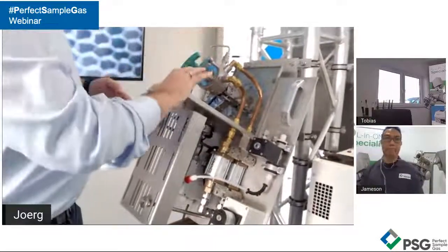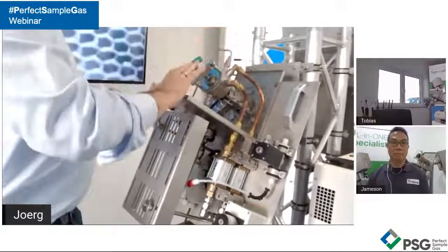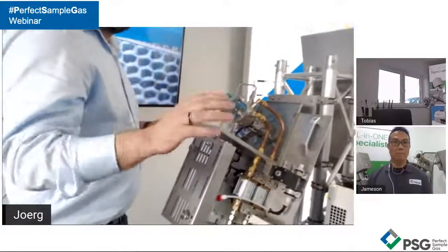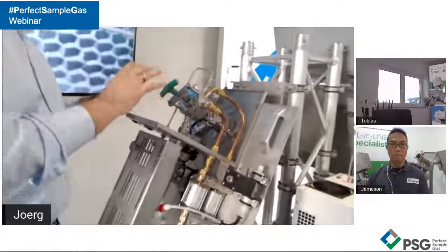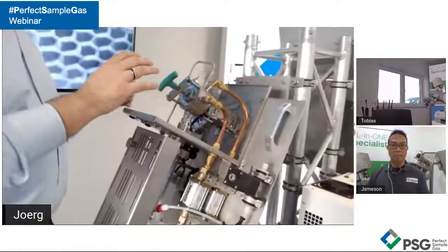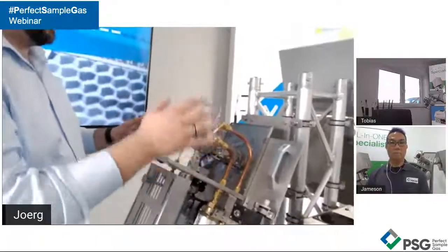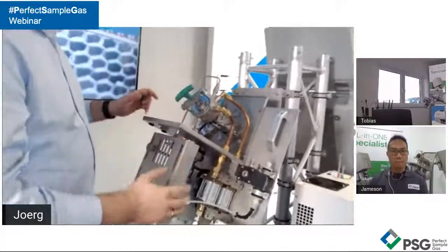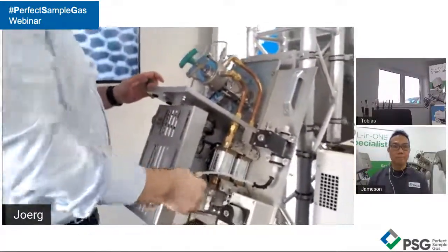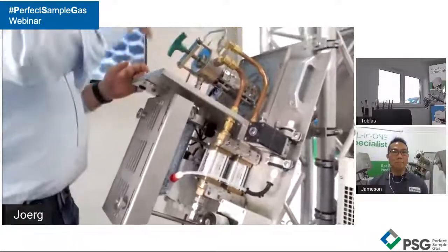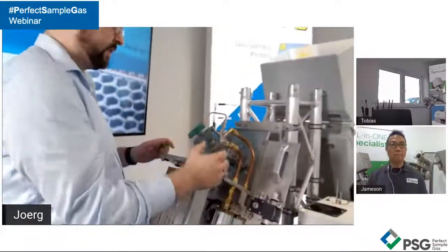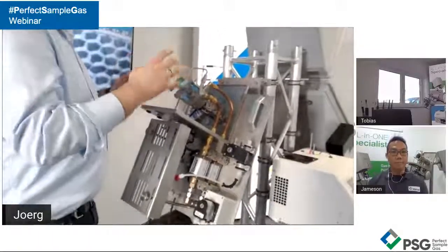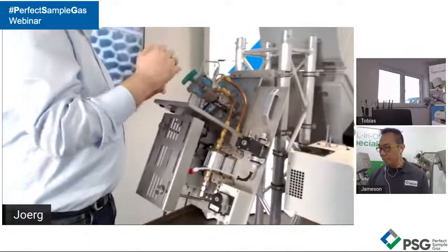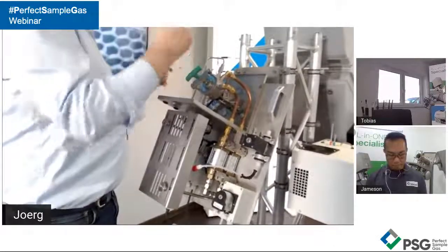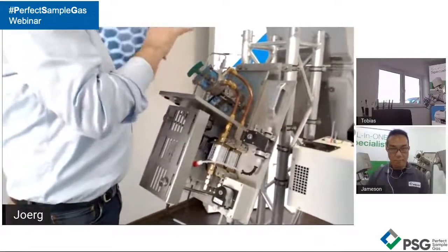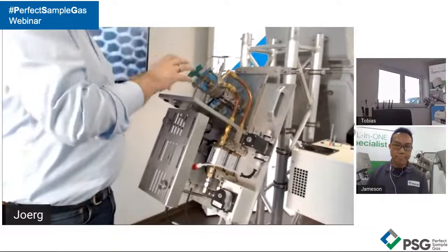Now, this probe is also with a back purge. It's not for the DeNOx application Jimson explained right here. It's a special application we used for a customer in a sewage sludge application. He was not facing the ammonia problem. He was just facing salt problems that come with temperature drop. But he still had the high dust problems. And therefore, he said, I need something to lower my maintenance interval, no matter how low, but give me the best you can do, so that the guys don't need to go out to the probe anymore.